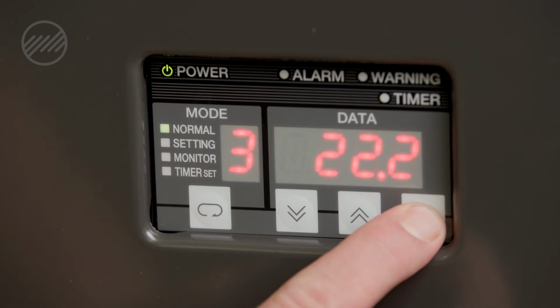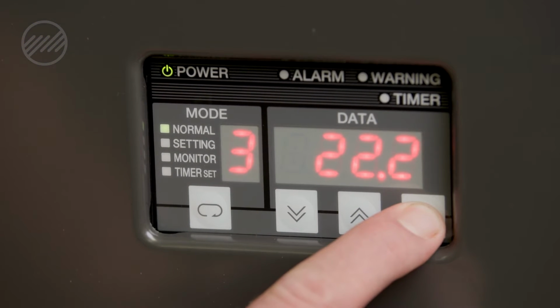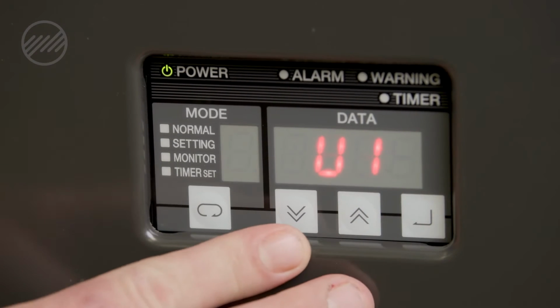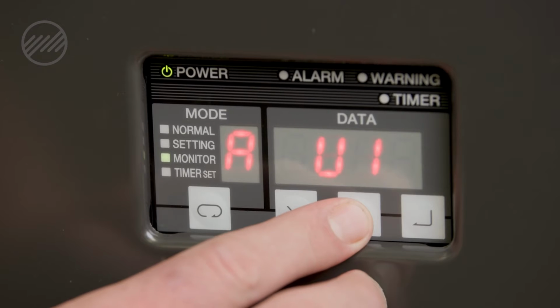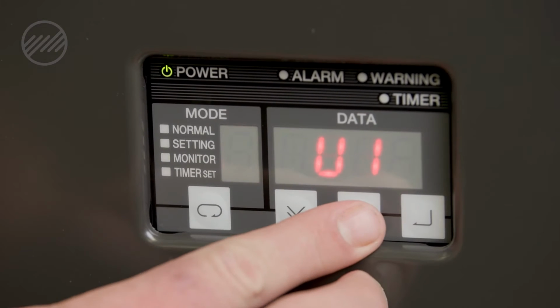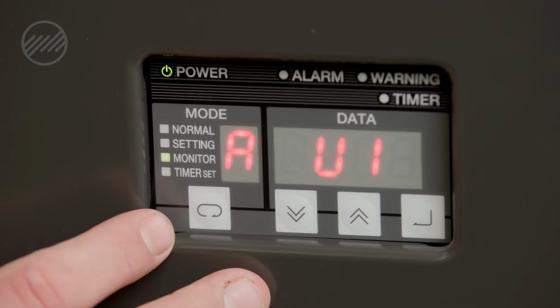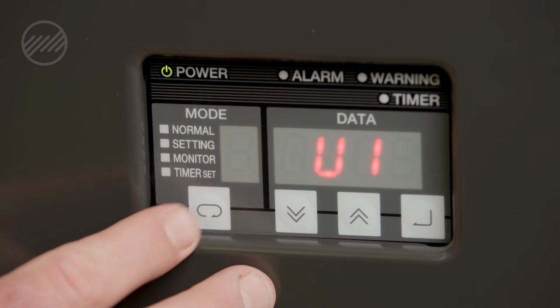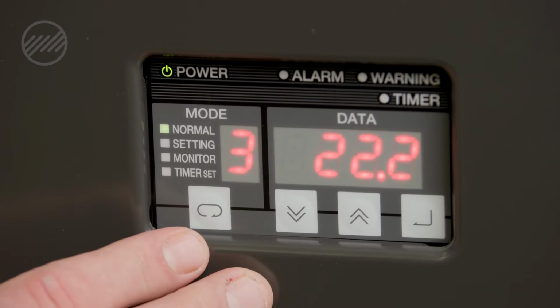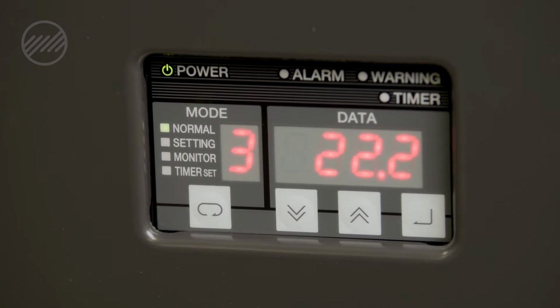To access your alarm history, you will hold the right-hand button until you see the alarms pop up. This will give you the ability to scroll up and down through each alarm in the history to help with the diagnosis. To get out of the alarms, you'll press the enter button all the way to the left, and you'll be back in your standard mode screen.